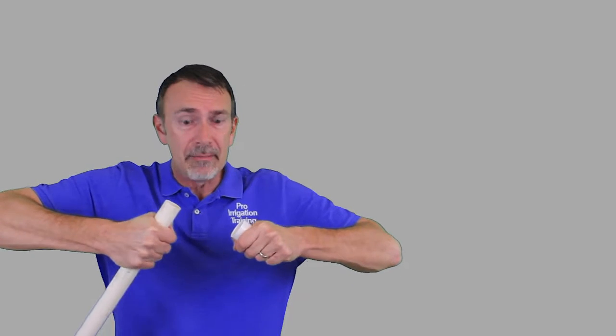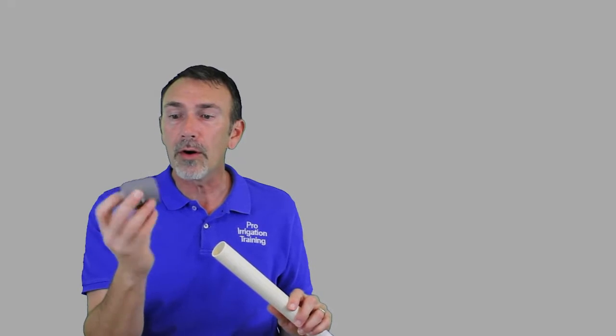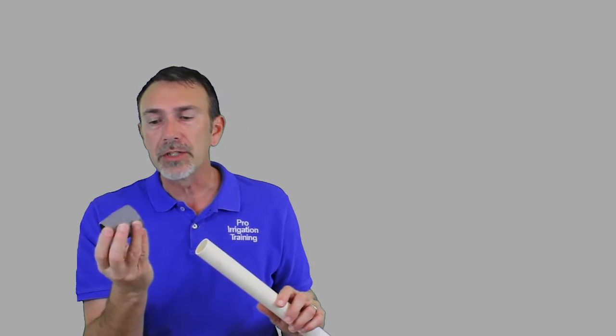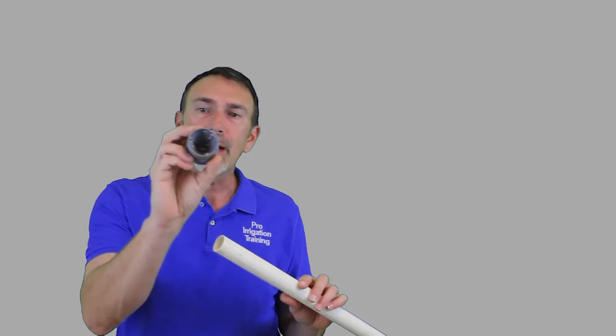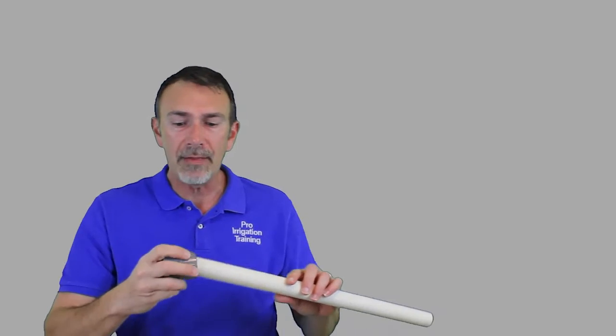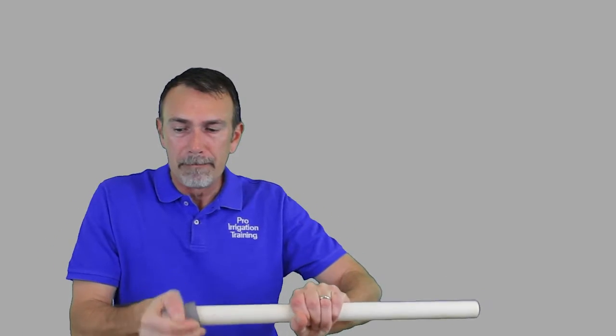But if you're making a repair, and let's say you've got this pipe bent back and we're doing it old style and we're just going to use a simple coupling on this, and as we put this together and we're forcing it down, this edge here may actually scrape away part of the PVC on the inside of our fitting. When we talk about the solvent selection and the primer, we'll see how that primer softens this up, but it'll still tear pieces away. So what we want to use is a deburrer. This here is a deburrer. It's also got a reamer, but chances are you're never going to need to ream your pipes out. But we may want to bevel that edge, so it has little blades on the inside there. When you put this thing in and kind of grind that edge off, it'll leave you with a little bevel there.